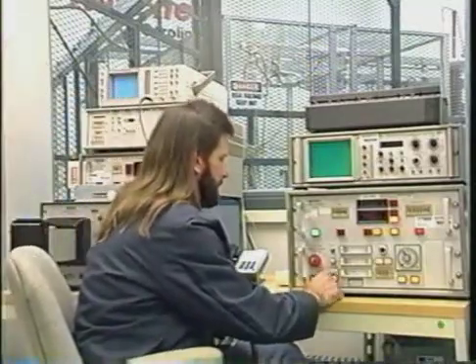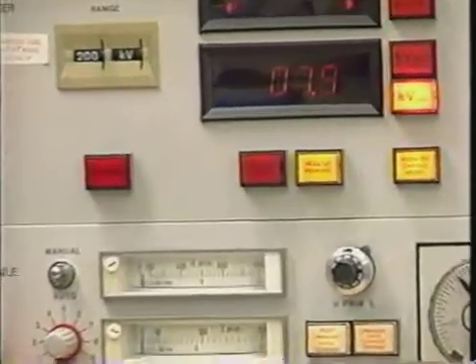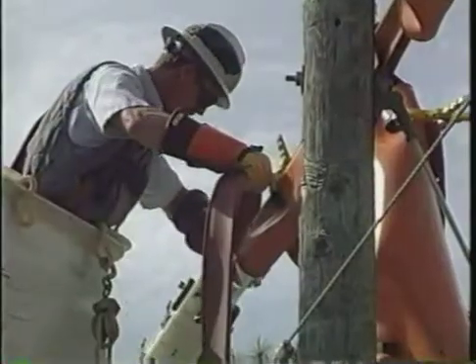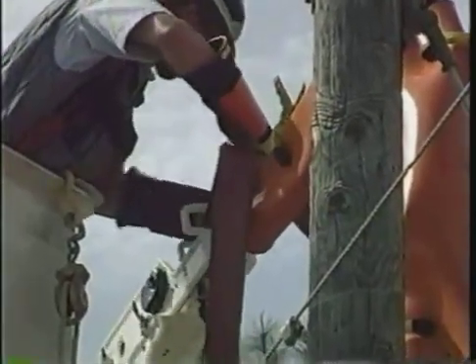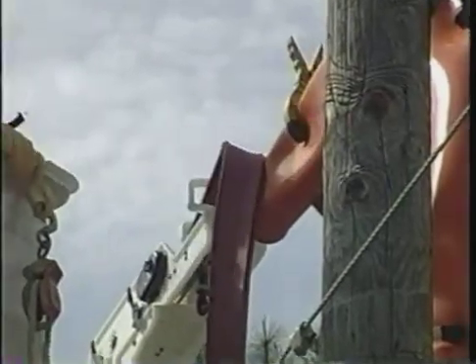This is an example of one specific situation done in a controlled laboratory environment. Actual field results will vary greatly depending on the type of tree branch, age of the branch, and other environmental conditions. However, the installation of MVLC significantly increases the resistance to branch-induced fires and reduces electrical arcing in wet and dry environments.